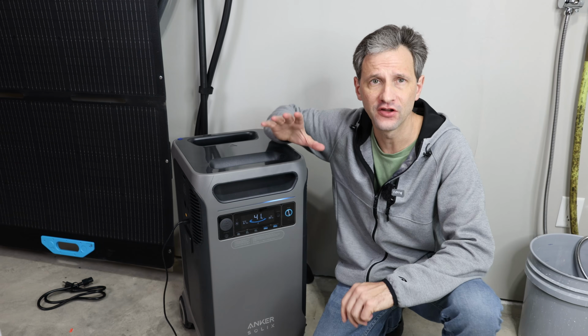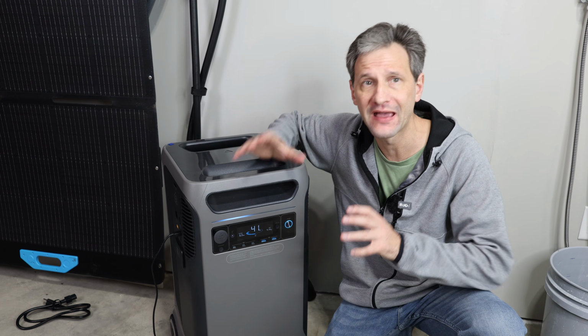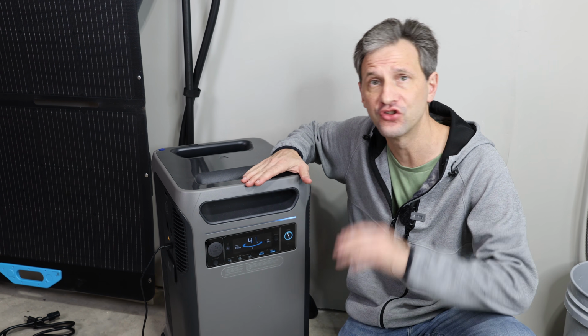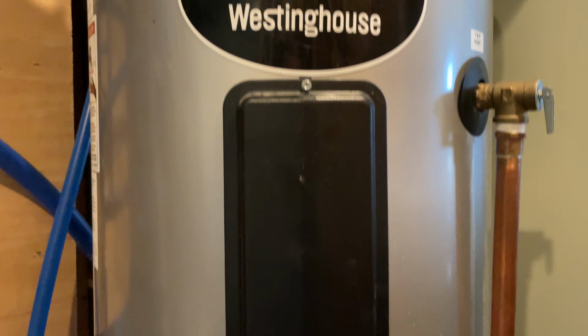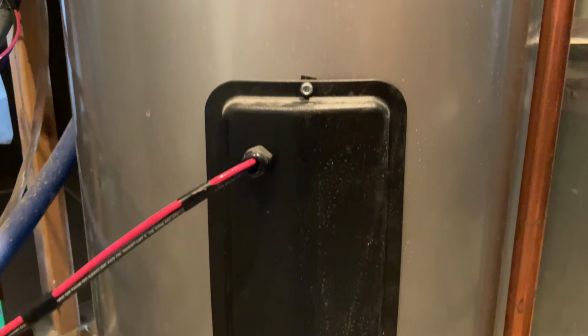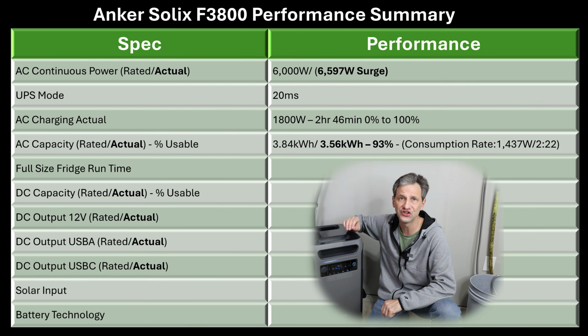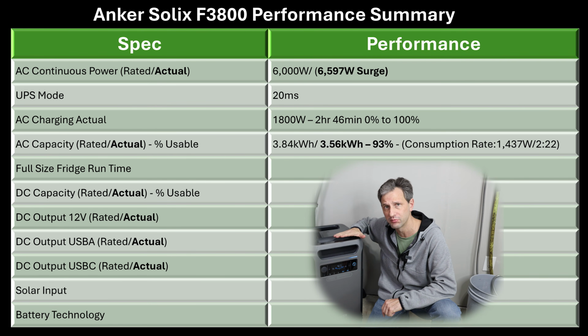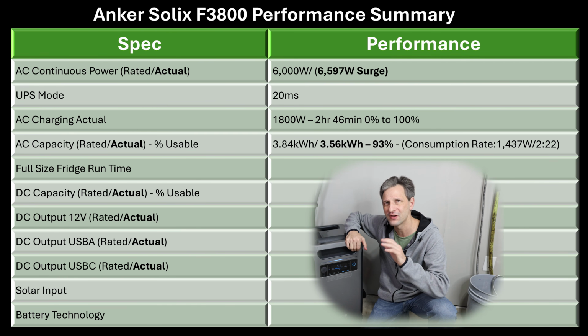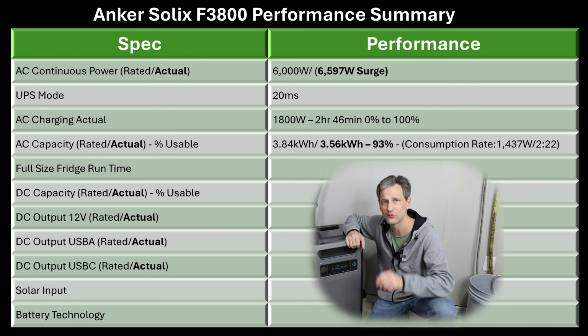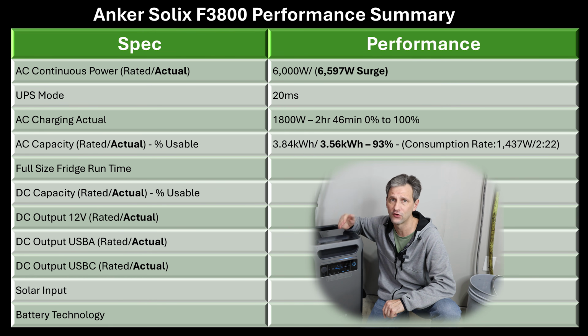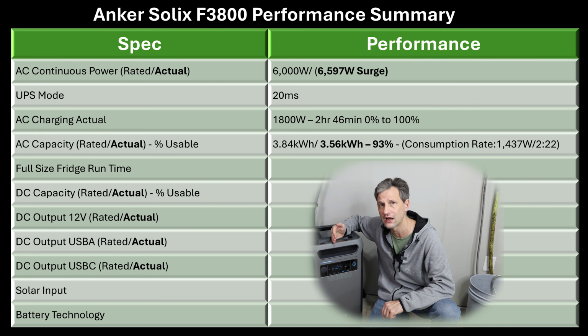To get an understanding of the available AC delivered battery capacity, I charged the battery to 100% and connected it to my home water heater, which provides a nice mid-range constant 1437 watt load. It took 2 hours and 22 minutes to deplete the battery and consumed 3.56 kilowatt hours, which is 93% of the rated 3.84 kilowatt hour capacity.